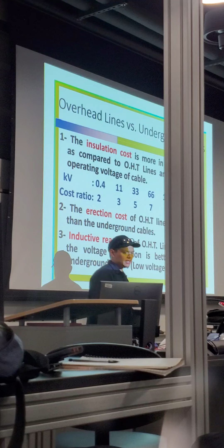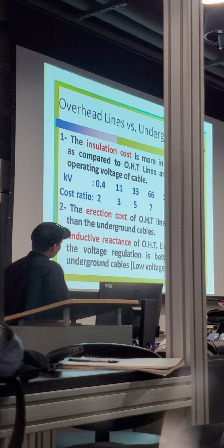Inductive reactance of OHT lines is more, so the voltage regulation is better in the case of underground cables, meaning a lower voltage drop. Inductive reactance relates to the spacing used in transmission lines so it doesn't negatively affect each other, whereas that's impeded by the underground nature of the insulation - another consideration when speccing out overhead lines versus underground cables.